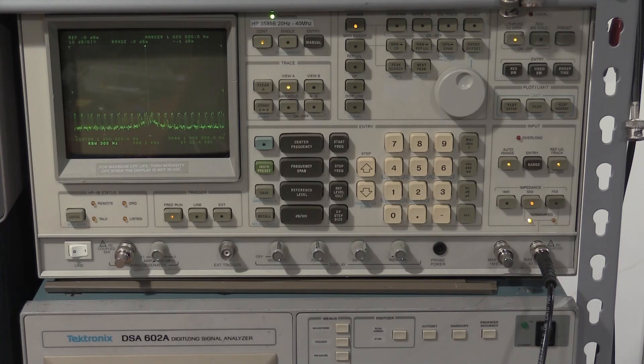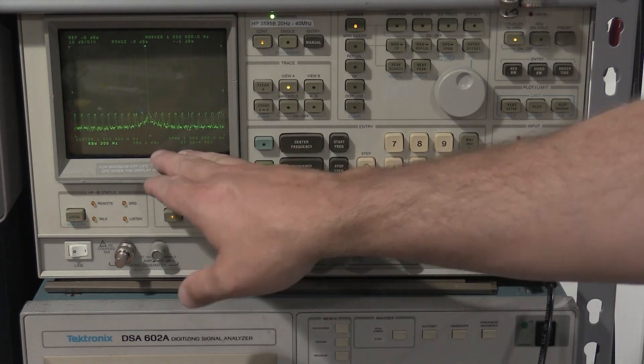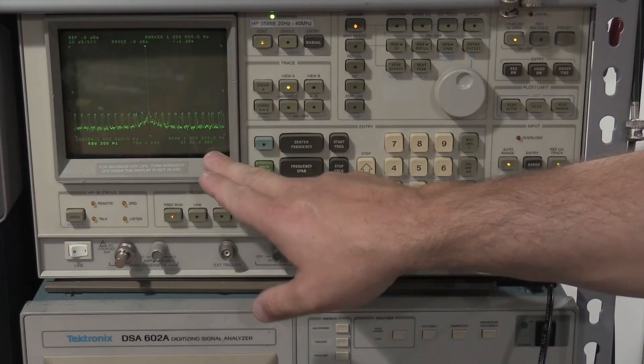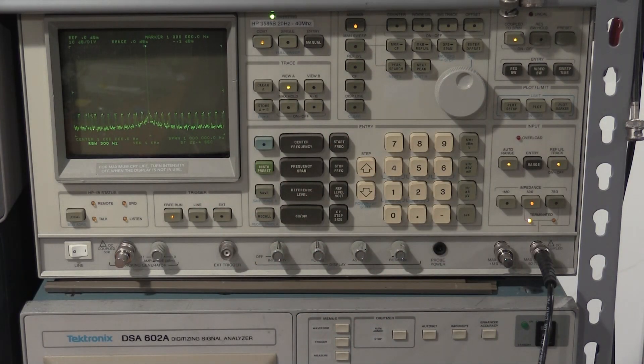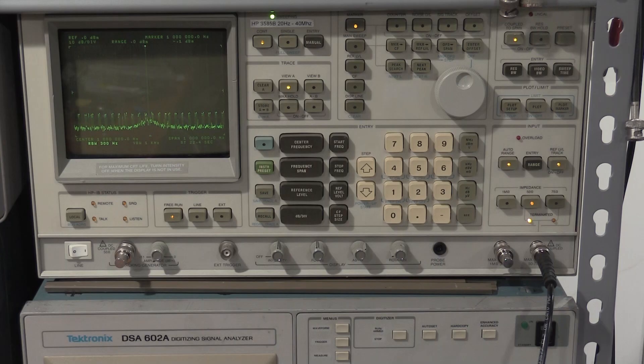But there's a couple things that immediately sprung to mind, just given the way I have the lab set up. One was, I have an energy monitoring system that does use power line networking for some data transfer rates. That was the first thing that popped through my head. This could be common mode noise coming in on either the neutral or the ground line, probably the ground line, and it's messing with the ground reference. As the ground reference is moving, the measurement plane of this device is moving up and down with those high-frequency chirps on the ground line. Especially with it being regular like this, first thing we're going to try is unplugging that power meter.